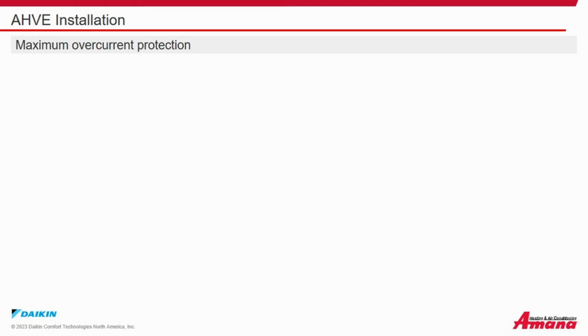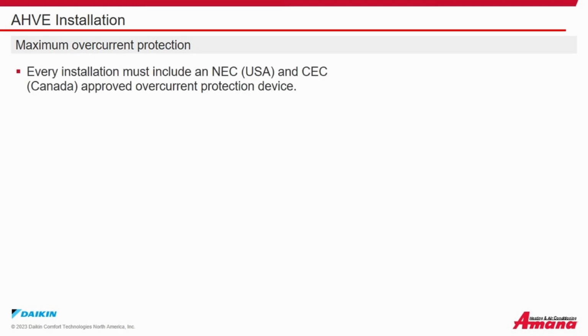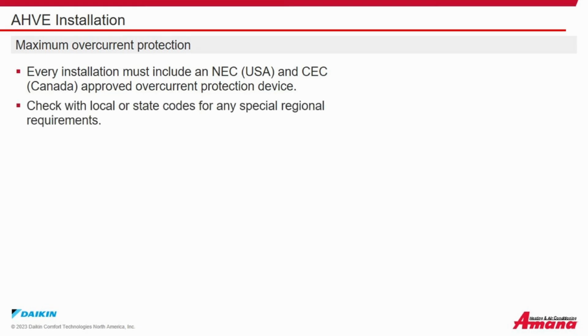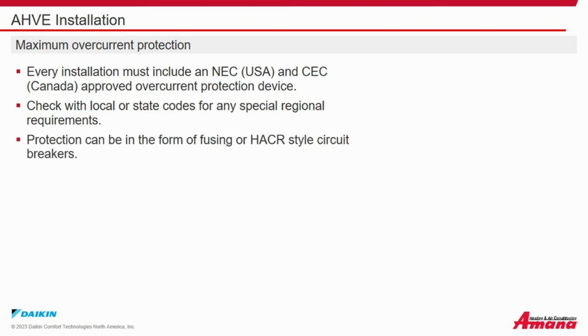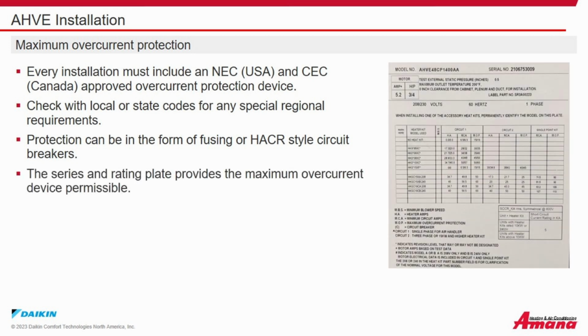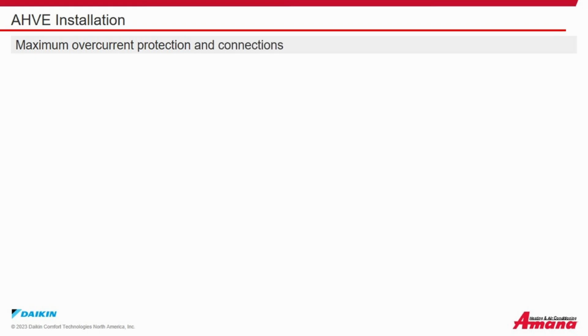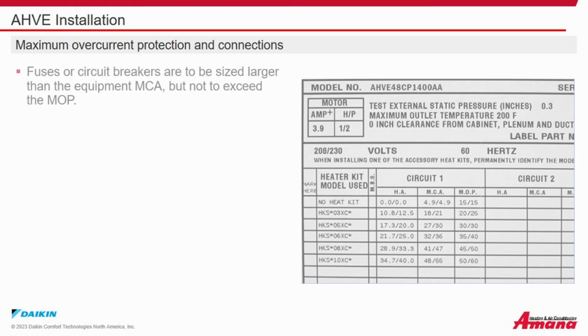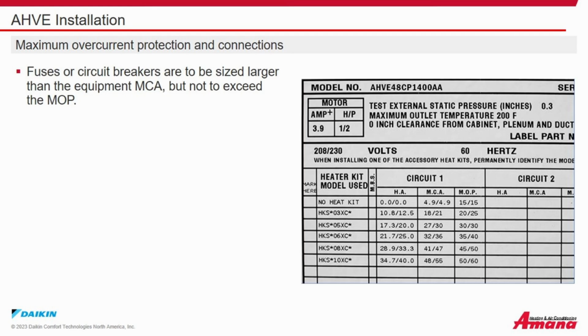Maximum overcurrent protection. Every installation must include an NEC approved overcurrent protection device. Check with the local or state codes for any special regional requirements. Protection can be in the form of fusing or HACR style circuit breakers. The series and rating plate provides the maximum overcurrent protection device that is permitted. Maximum overcurrent protection and connections. Fuses or circuit breakers must be larger than the equipment's minimum circuit ampacity, but not to exceed the maximum overcurrent protection.